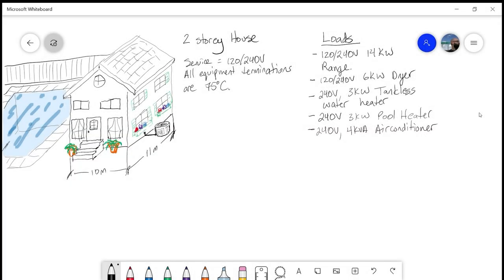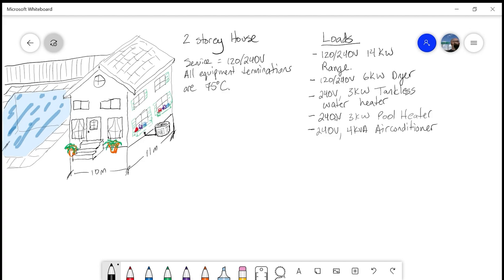I just wanted to quickly do an additional house calculation. It's a two-story house, service is 120/240 volts and all equipment terminations are 75 degrees Celsius. We have a 120/240 volt 14 kilowatt range, a 120/240 volt 6 kilowatt dryer, a 240 volt 3 kilowatt tankless water heater, a 240 volt 3 kilowatt pool heater, and a 240 volt 4 kVA air conditioner. Specifically, what we're going to do with this video is determine whether it's going to be 8-200(1)(a) or (b).